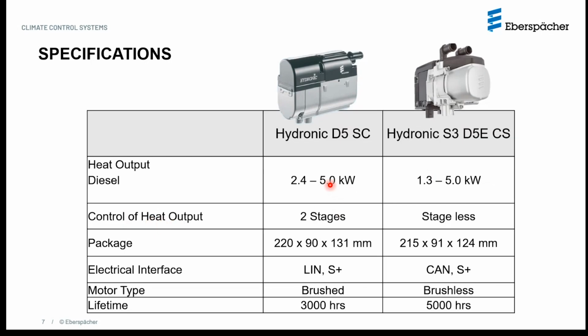Now, as far as controlling the heat output, when you switch on the heater, it will always begin operating at 5 kilowatt or 17,000 BTU. But as the temperature of the coolant starts to rise, then the heater will switch to a lower output. In case of the first generation, there were only two heating stages defined, so it could only operate in those two heating stages. The first one was defined as the high heat output, which is 17,000 BTU or 5 kilowatt, and the next stage was the 2.4 kilowatt stage. In case of the Hydronic third generation, the S3 heater, it is stageless. It's more like a variable output. So there will be small incremental steps, and the output will be reduced gradually till it reaches the lowest point. This allows for a much better control of the optimum temperature of the coolant, much more efficient operation of the heater.